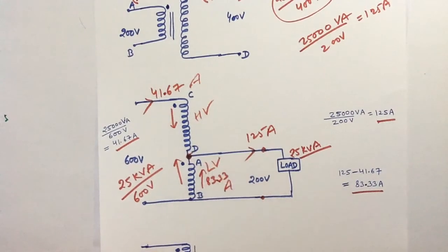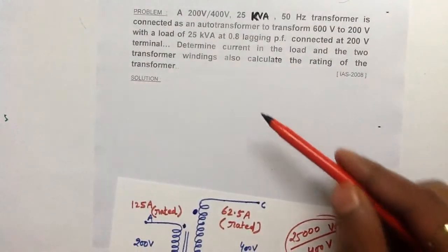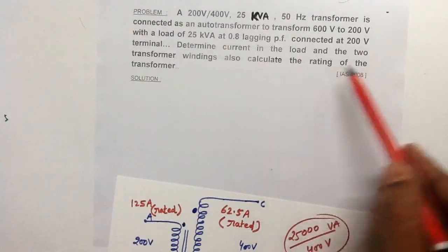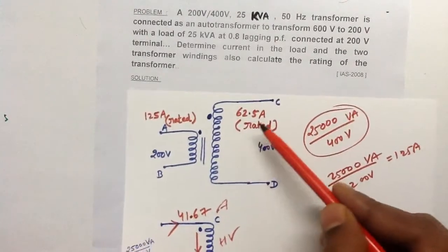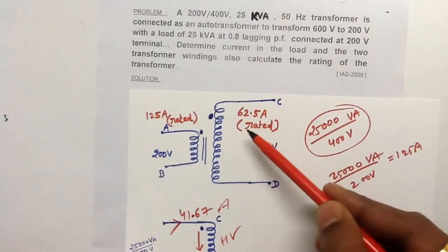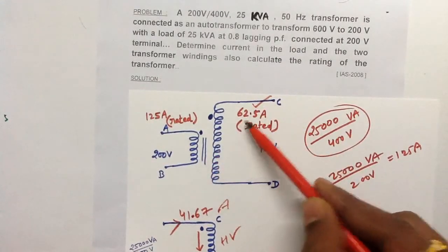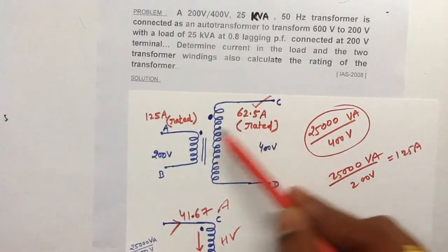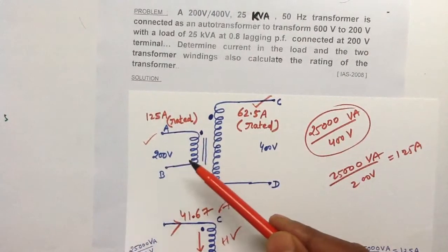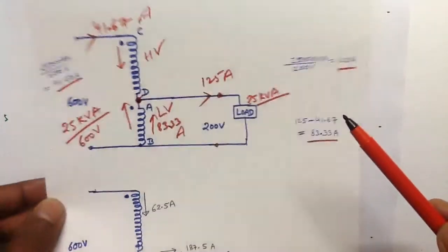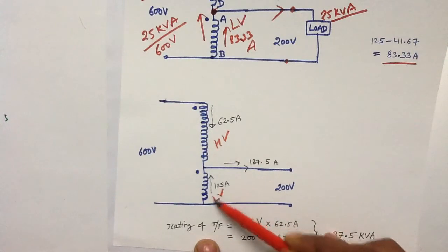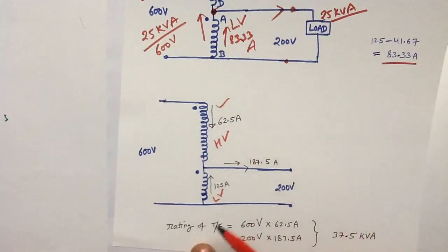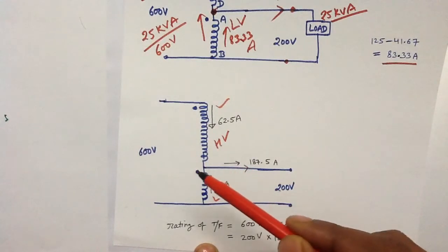The second part of the question is to calculate the rating of the autotransformer. To do this, rated currents must flow in both windings. The rated current in the HV winding is 62.5 amperes and the rated current in the LV winding is 125 amperes.